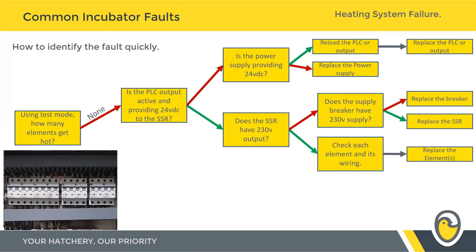If your solid state relay does have output — it's putting out a clean 230 or 110 volts — but your heating elements aren't getting hot, check each heating element and its wiring. The heating elements on an individual zone are all wired in parallel, so it's exceedingly unlikely that one going down will impact the rest. However, if you've got a short on the system, you can find the breaker repeatedly tripping. At this stage of fault-finding, it's worth swapping out individual heating elements to rule them out one by one.